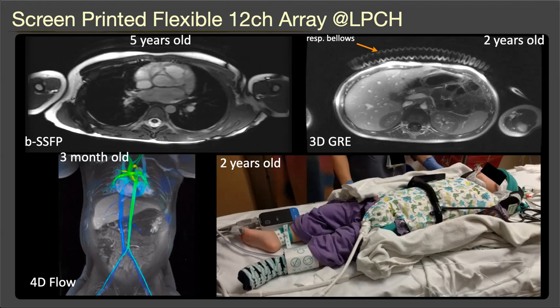So if you notice here, the respiratory bellows are actually on top of the coil. Usually that's not the case - usually you put them underneath, but because this coil is very flexible, you can actually put it on top. The top image is a short echo time image, which shows the signal from the bellows cover. Now note that the curve is where the coil is in close proximity to the body for maximum SNR. So the coil is actually underneath the bellows, and you can see the really strong, very nice signal.